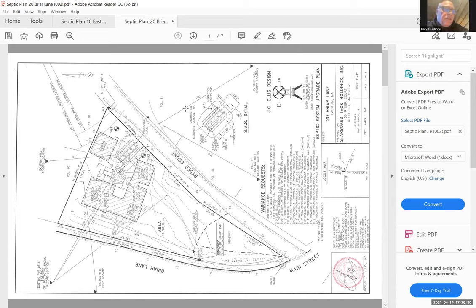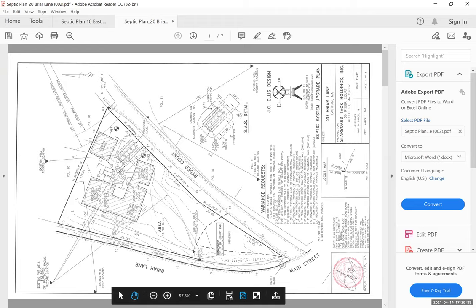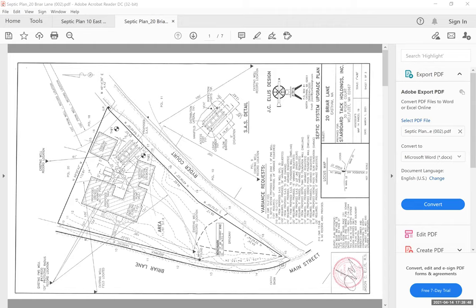That, and I think there should be at least one clean out on each building sewer line, so that'd be three clean outs anyway. That's fine. And the other thing that we could do with the orifice shields, as we've done before, is you take a piece of either schedule 80 or schedule 40 8 inch diameter pipe, cut it in half. I love that much better. I use that myself. Yep. Revise it to show that. Okay.